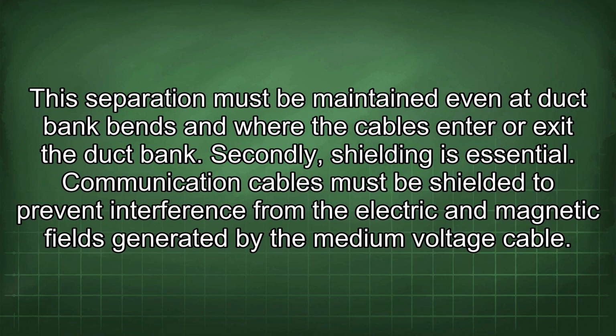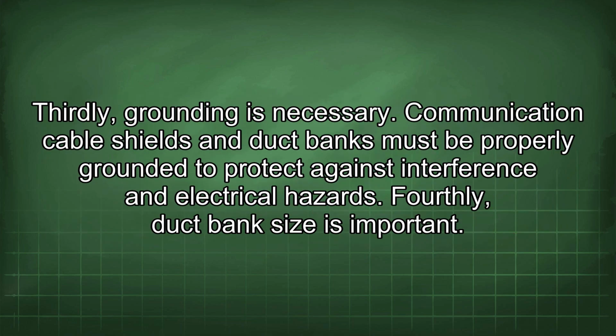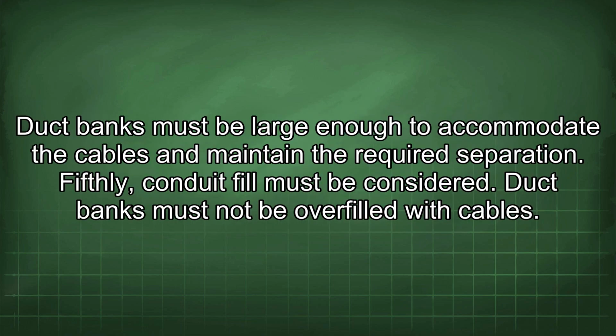Secondly, shielding is essential. Communication cables must be shielded to prevent interference from the electric and magnetic fields generated by the medium voltage cable. Thirdly, grounding is necessary. Communication cable shields and duct banks must be properly grounded to protect against interference and electrical hazards. Fourthly, duct bank size is important. Duct banks must be large enough to accommodate the cables and maintain the required separation.